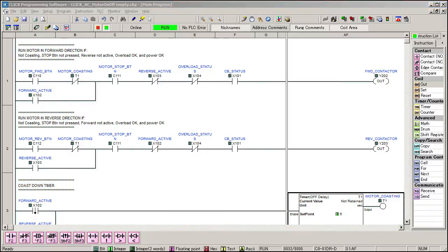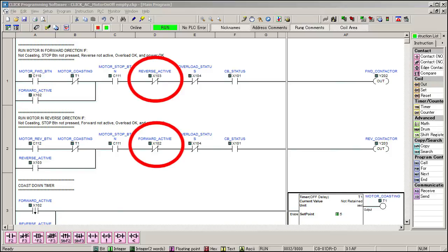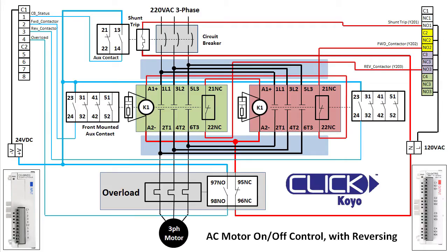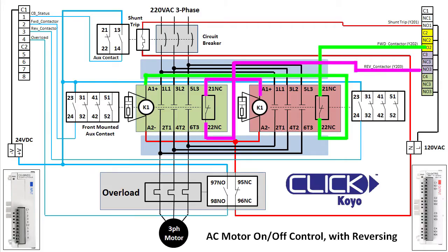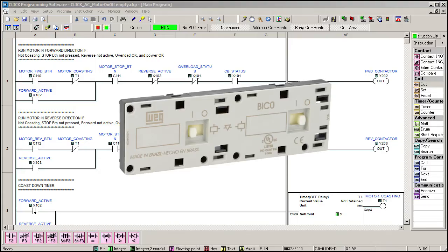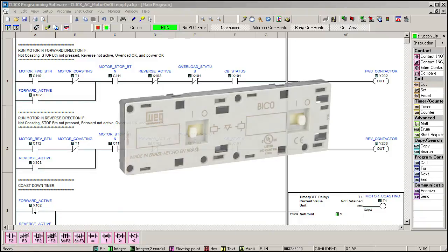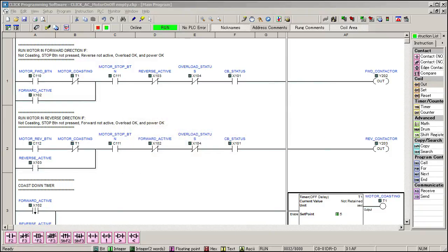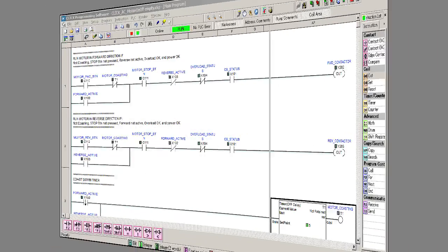It's important to understand that with the addition of this code, we are now protecting our control system with triple redundancy. We prevent the motor from running in one direction if it is already running in the other direction. We have fail safes here in the code, here in the wiring, and mechanically with an interlock block. That creates a super reliable, fault tolerant system.